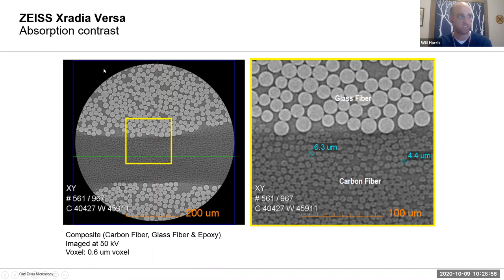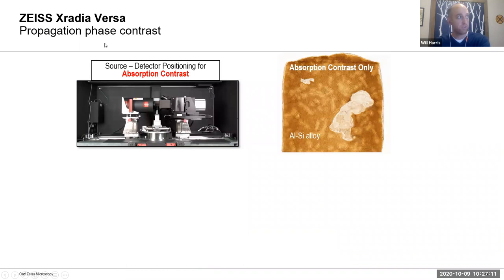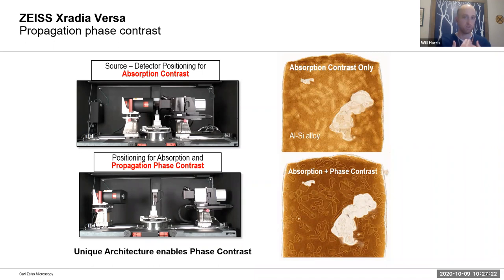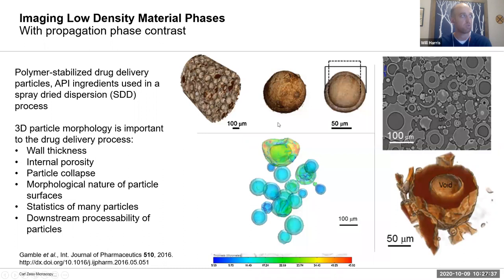Absorption is exactly what it sounds like — an attenuation-based contrast mechanism that works on the average atomic number of the individual phase, so we can differentiate things like different types of fibers in a composite material. Phase contrast is a way of leveraging differences in propagation speed of the x-rays — no longer their attenuation, but the other component of the refractive index, which is a relative phase shift through different regions of material.